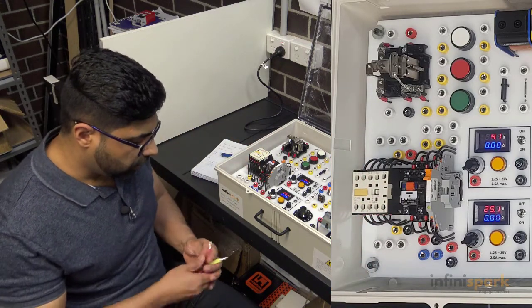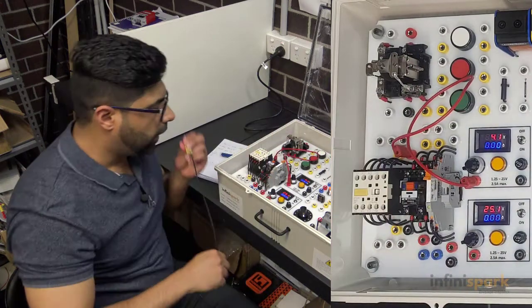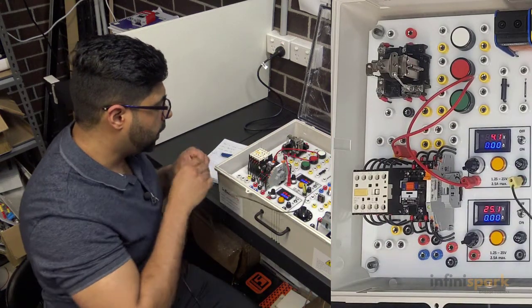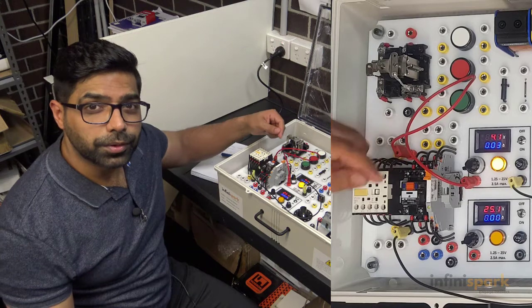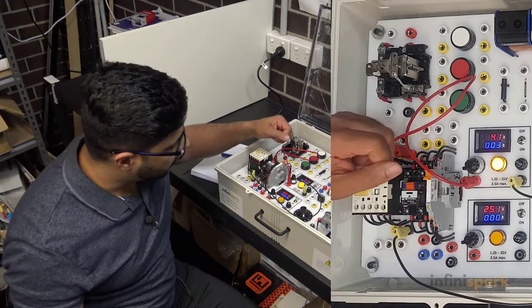The positive side of the power supply goes to the positive side of the coil, and the negative of the power supply goes to the negative side of the contactor coil. If I turn it on you see how nothing happens. I'm going to increase the voltage to find out the pull-in voltage of this contactor.